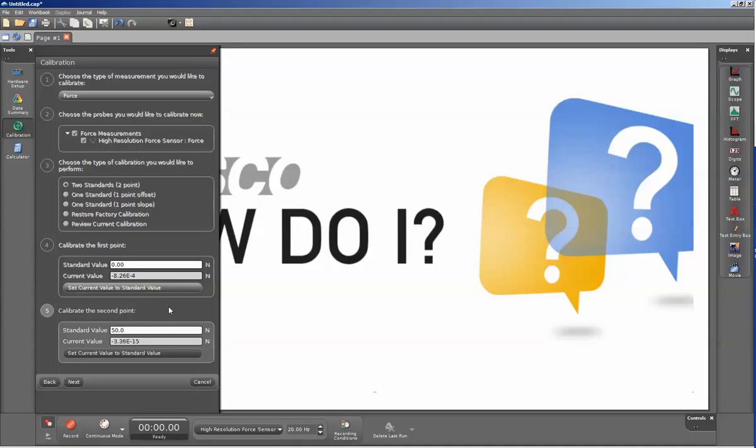So I'm now going to very gently hang my known mass from the hook, and you'll see the values changing there. I have a much smaller mass than the full 50 Newton value that the sensor can take. It's best to use a larger mass than this so that you can have it calibrated over the full scale of the sensor.